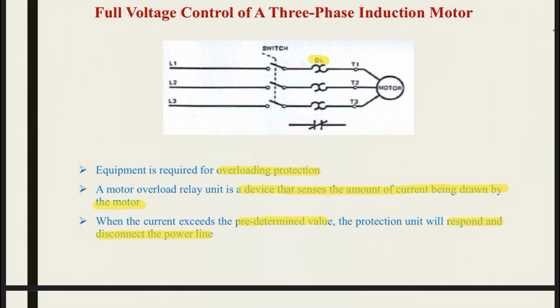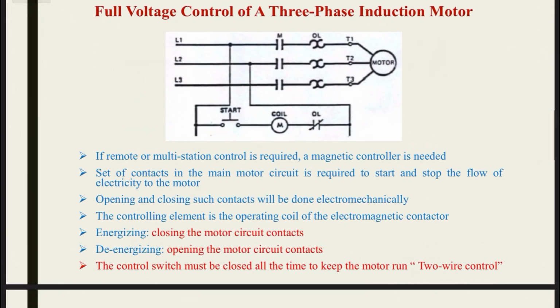Next slide now. If remote or multi-station control is required, a magnetic controller is needed. Now we will install the magnetic controller. A set of contacts in the main motor circuit is required to start and stop the flow of electricity to the motor. Opening and closing such contacts will be done electromechanically. The controlling element is the operation coil of the electromagnetic contactor. This is the main coil.